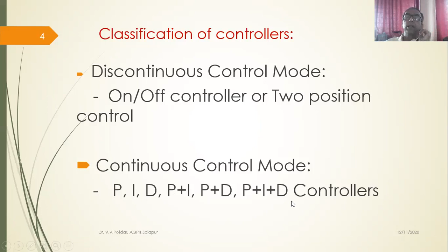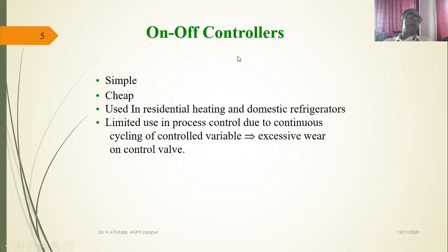Let us see the first case, on-off controllers. Why are they preferred? They are simple to operate, only two position control. They are very cheap. So cost-wise also it is cost-effective, used in residential heating and domestic refrigerators. The refrigerator is put on and put off. The thermostat that is used works on the on-off principle. There is limited use in process control industries due to continuous cycling of control variables and excessive wear of control valves. So in continuous process industries, these on-off controllers are not used.